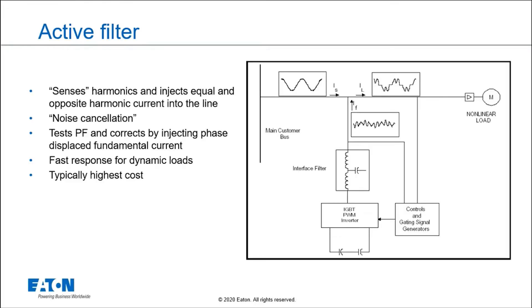Now if you take a look at this, basically you have harmonics coming out of the load from the right, from the non-linear load, which would be a drive, and in the middle part we have the active harmonic filter, which is kind of like a noise cancellation system that injects equal and opposite frequencies of everything but the 60 Hertz.